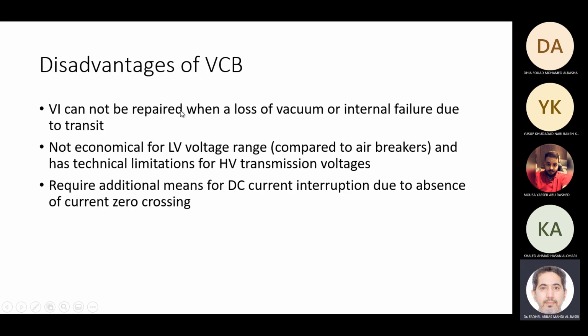But they have a disadvantage. They cannot be repaired because you cannot open them. Okay, if you lose the vacuum or there is an internal failure, you cannot open it. So you lose it. That's it. It's not economical for low voltage systems. That's why we don't use it for low voltage breakers, as compared to air breakers. Air breakers are dominantly used on low voltage systems. And vacuum has technical difficulties at higher voltage. That's why it is very commonly used on medium voltage applications.